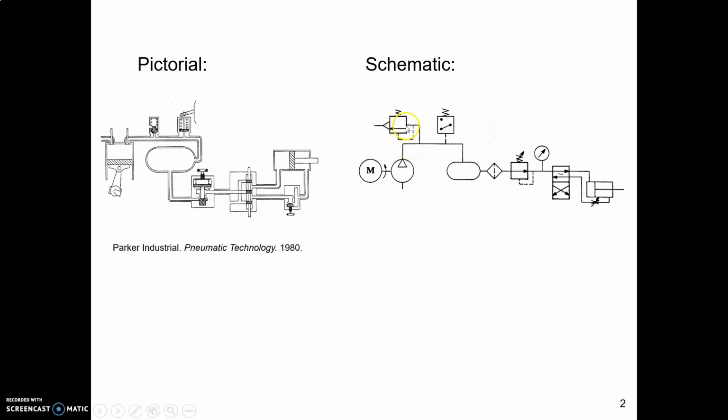Here is a pressure relief valve, and we can see that there's a spring that determines when it releases air or not. Then here's the triangle indicating that excess air is exhausted into the atmosphere. Then here's the symbol for the receiver, our pressurized air tank. Here's a filter. Here's our pressure regulator, and this system has a gauge on there. Here's our valve, and then here's our double acting cylinder, and looks like they have an adjustable flow control valve.